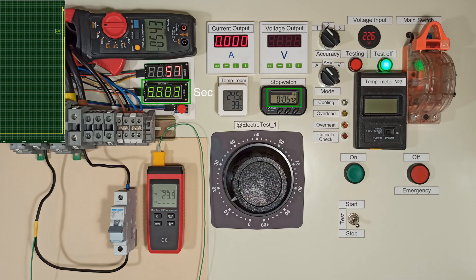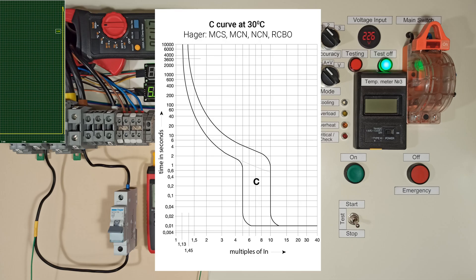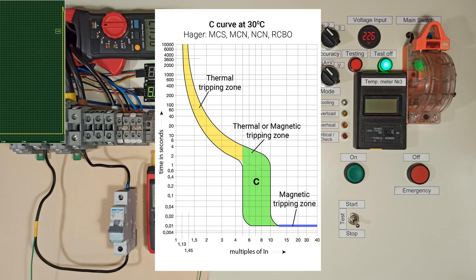The tripping time of circuit breakers depends on the current, and it can be calculated by knowing the curve. Characteristic graphs have three zones: tripping by the thermal element, tripping by the magnetic element, and a transition zone where tripping may occur either by the thermal or the magnetic element.